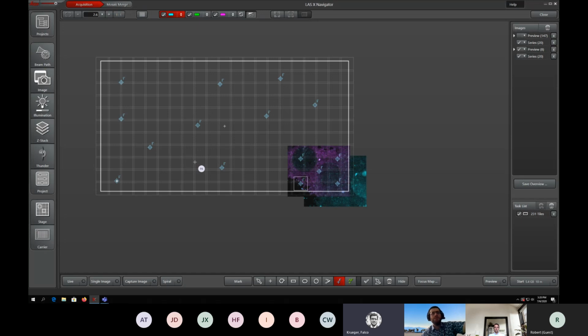Because what is happening, I'm not focusing on each and every image. You could do this as well, but this takes a lot of time and is not feasible for everyday imaging workflows. What happens with the focus map points is that to the lateral X and Y coordinate, you enter a Z coordinate. So you're creating a 3-dimensional point. If you have several of those points, you are creating a 3-dimensional map where you have the individual focus map points being laid out. And in between those focus map points, the height of the images that don't have their own focus points are being linearly extrapolated, okay?